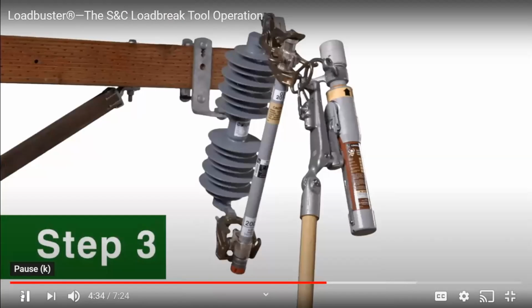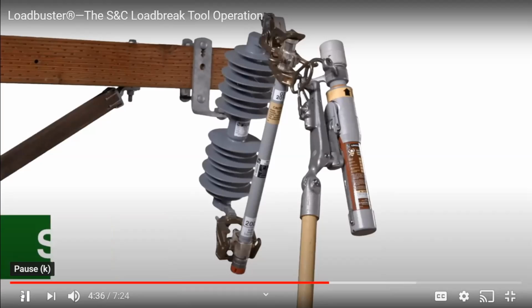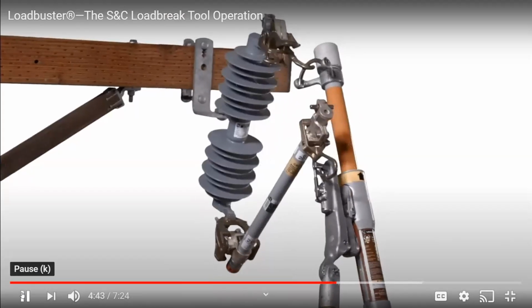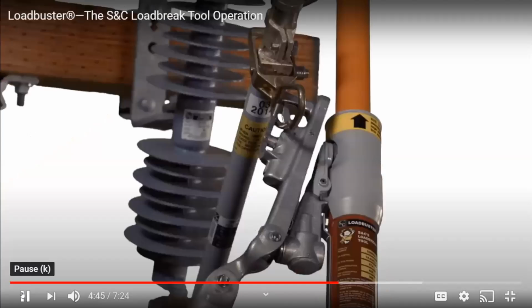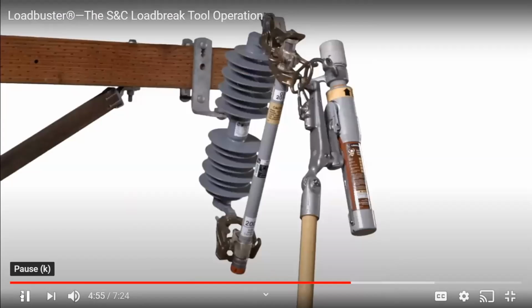Step 3. To open the circuit, operate the Loadbuster tool with a firm, steady pull until it is extended to its maximum length. Avoid jerking and hesitating. The resetting latch will keep it open. Generally, there will be no indication of circuit interruption, but minor arcing may be noted at the pull ring hook and at the anchor, particularly when interrupting load currents approach the rating of the tool.